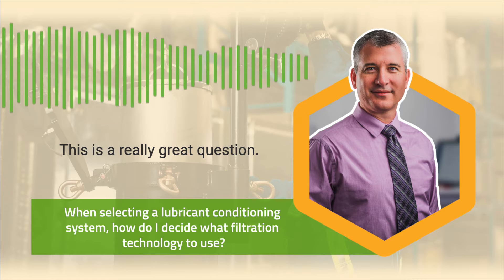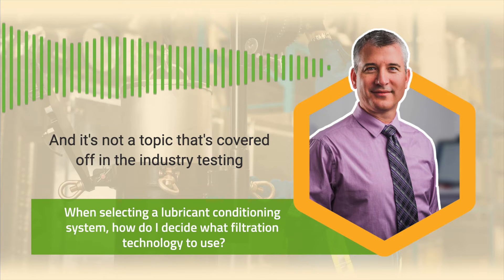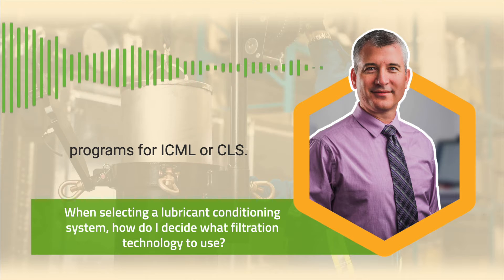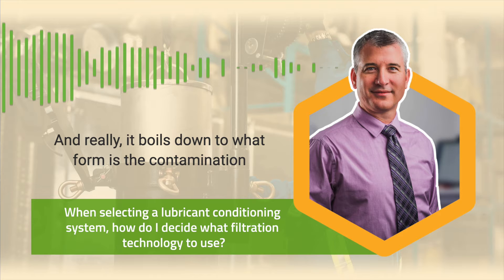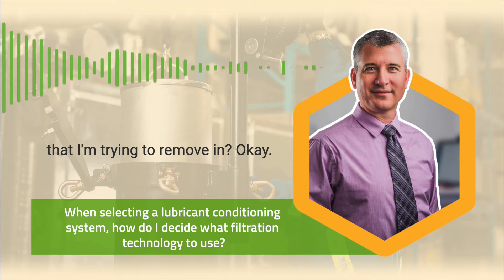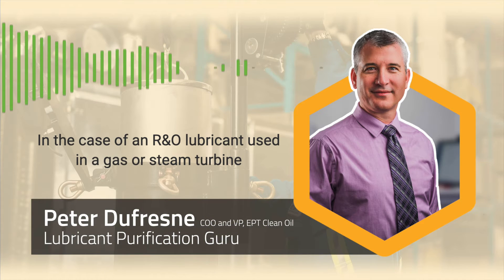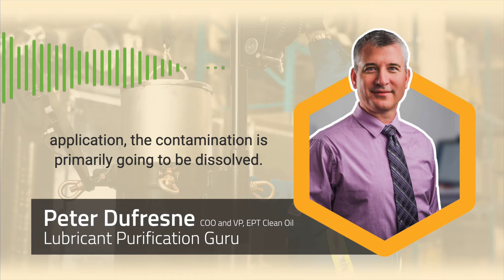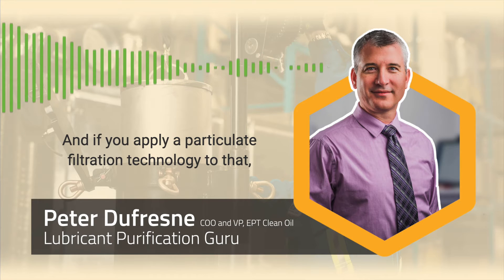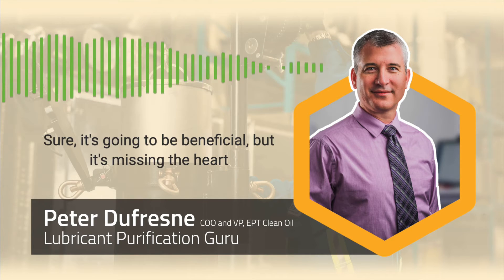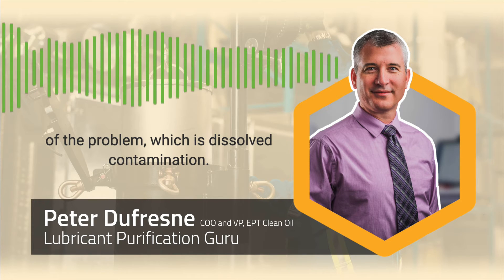This is a really great question, and it's not a topic that's covered in the industry testing programs for ICML or CLS. It really boils down to what form the contamination I'm trying to remove is in. In the case of an R&O lubricant used in a gas or steam turbine application, the contamination is primarily going to be dissolved. If you apply a particulate filtration technology to that, it's a mismatch — it may be beneficial, but it's missing the heart of the problem, which is dissolved contamination.